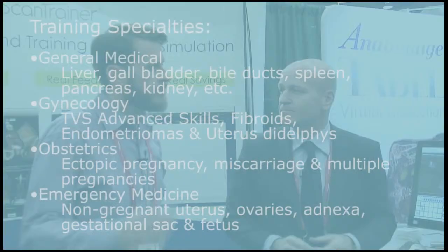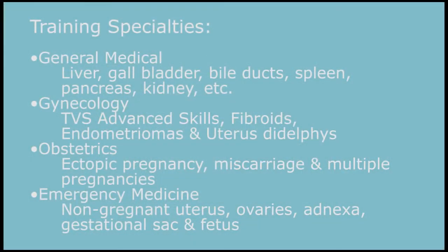So we could take very different sized patients — from pediatric to geriatric and everything in between — and scan those images and experience the differences through the device. We program the patient into the simulator. So you might start as a 12-week pregnancy, then go to 20-week, then 27-week pregnancy. The whole time the belly's changing in size and feel, programmed into the simulator. You feel that, and you also see everything about the scan changing. Some other ultrasound trainers out there have one body form — one mannequin — whereas this enables similar training but goes beyond by adding different case scenarios for different types of patients.